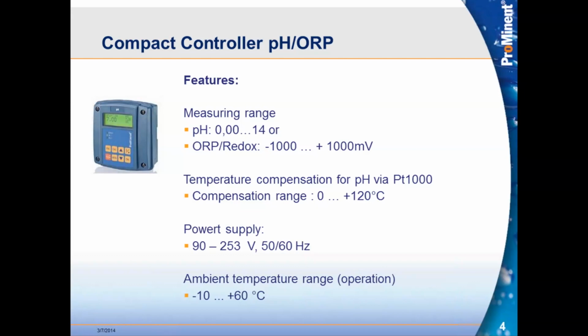So the measuring ranges we have to offer for pH, of course, is 0 to 14. People tend to refer to that as 2 to 12 typically. ORP redox is minus 1,000 to positive 1,000 millivolts, very common ranges for ORP sensors. Temperature compensation: we can offer temperature compensation for pH via a PT1000. They don't recommend you use the PT100. They're steering us towards the PT1000 for the compact controller.